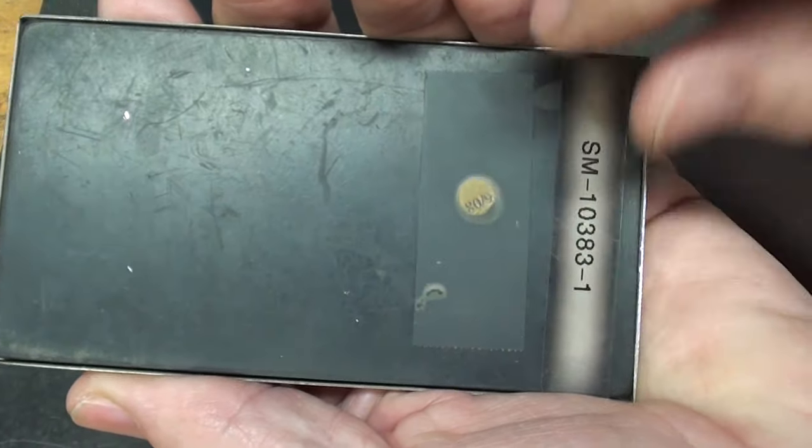About a half inch of travel. That's calculating and let's see what we got. That's hard to read. I have to raise the arm here so I don't damage anything. I've got 20 micro inches RA on the sample that reads 19, so it's mighty close isn't it?